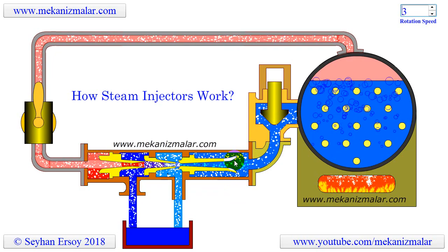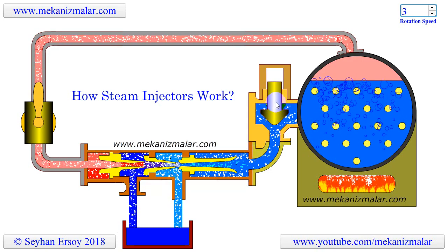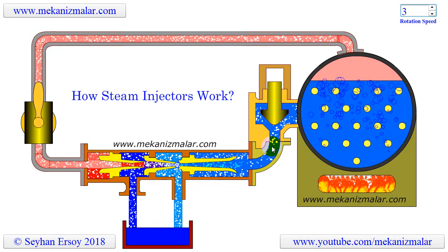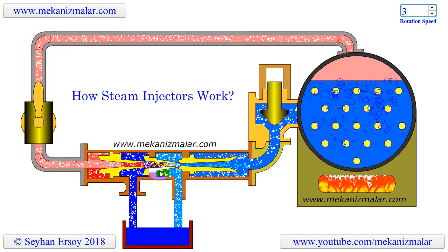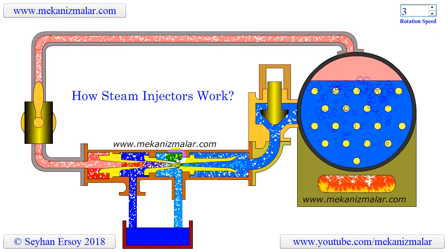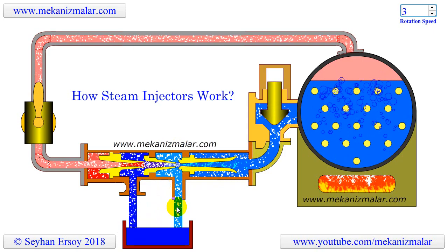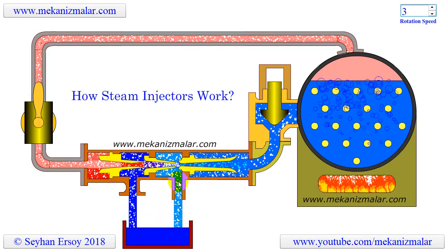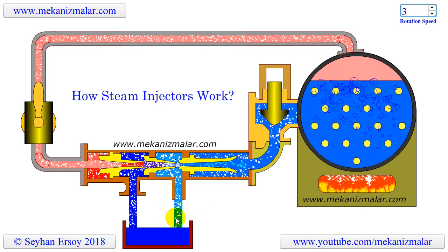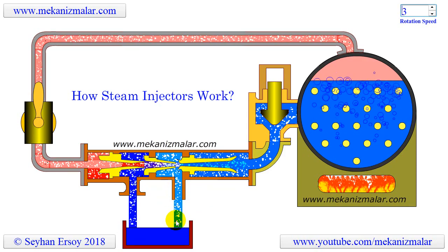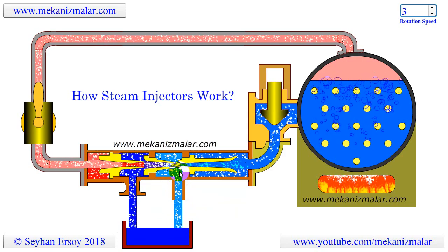What lies between the combining cone and the delivery cone is the overflow chamber. Adding this chamber to the steam injector was the ingenuity of the steam injector's inventor, Henri Giffard. This chamber and the overflow pipe allows the excess water to be sent back to the reservoir and prevents the steam injector from choking, especially when it is starting to operate for the first time. This allows the injector to operate smoothly.